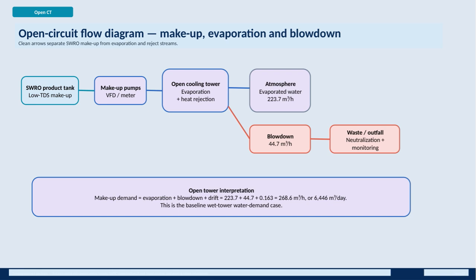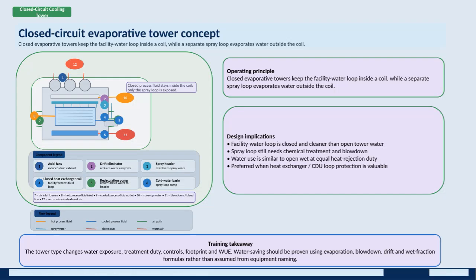and environmental management. Here we have the closed-circuit cooling tower, an important component in the integration of BATM's coastal data center water supply, including seawater reverse osmosis desalination and direct liquid cooling. The key operating principle here is that the facility's process fluid remains inside a closed heat exchanger coil, separated from the spray water that is sprayed over the coil and evaporates outside it. This separation means the process fluid loop is closed and stays much cleaner than an open cooling tower system.